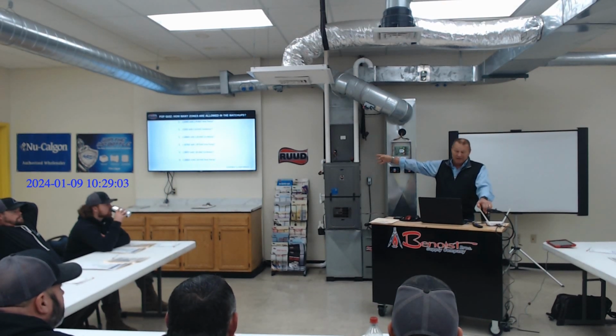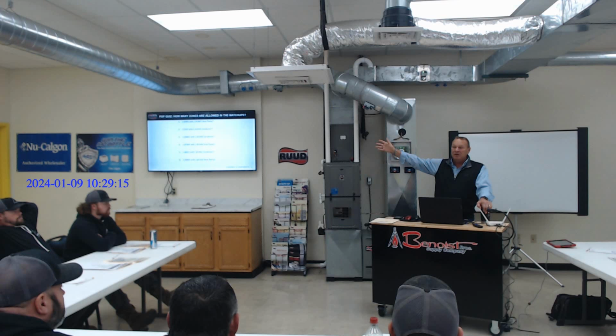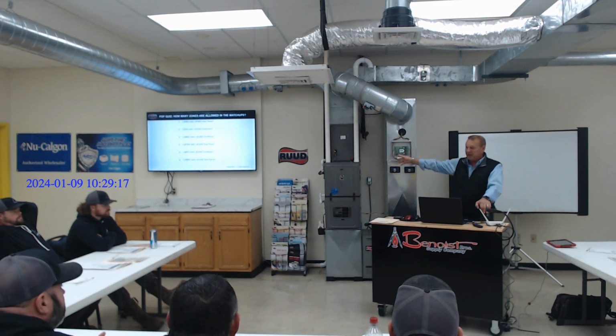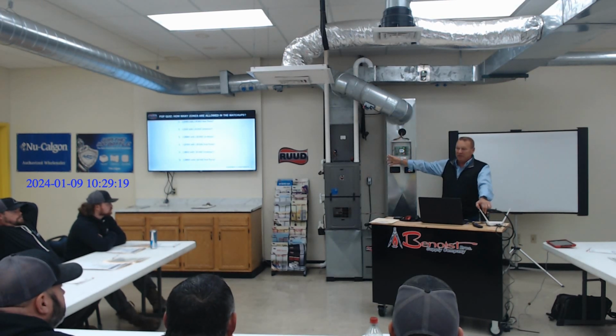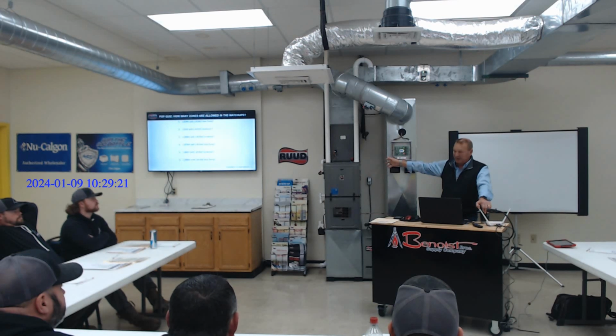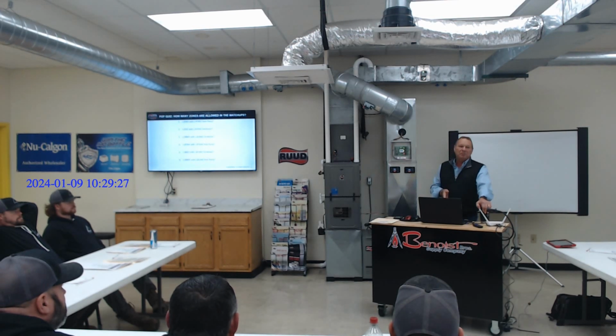But keep in mind, and again, this is one I ran into yesterday, so it's fresh. If I don't have 4 tons of airflow for the pump, I sure as hell don't have 1600 CFM for the electric heat if all 3 stages kick in either. So I can adjust the electric heat I put in the air handler too. I may want to think about an 18 kW or a 15 kW. Because if anybody sitting here has ever really done a heat load, you'll crack down both legs when you see the actual heat load of what you think needs to be in this house.